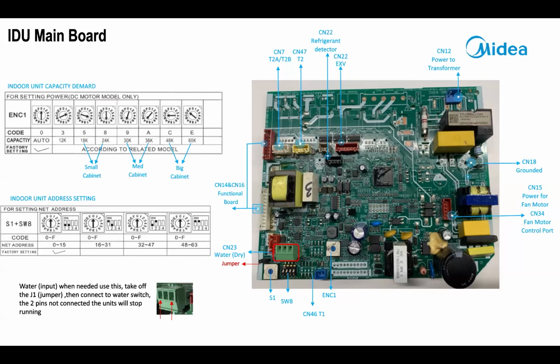Now, CN23, which is the most important part of this board. CN23 right here is your drain safety switch. If you put a drain safety in it, remember, the outer 2 terminals are the only 2 that are active. The middle terminal does nothing. That plug is removable. It's on the main board. You can pull that plug off of it, wire it, and then stick it back. If you're going to put an external drain safety on it, right next to it is this little black pin jumper. If you're going to put a drain safety on it, you must remove that pin jumper. Otherwise, the safety switch will never shut it off.